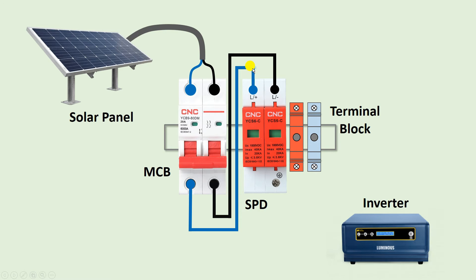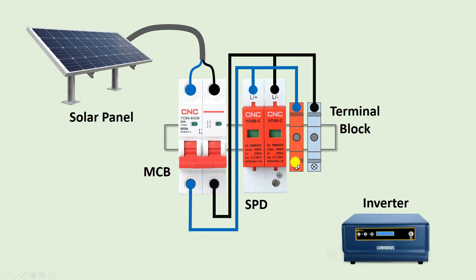On the negative terminal of the SPD, connect the negative power supply. So to this SPD we have provided the incoming power supply. Now from the positive terminal, connect a wire to the terminal block. Take the negative wire and connect it to the terminal block as well. The power supply going to the inverter must come from these terminal blocks, so connect wires from the terminals and provide power supply to the inverter.